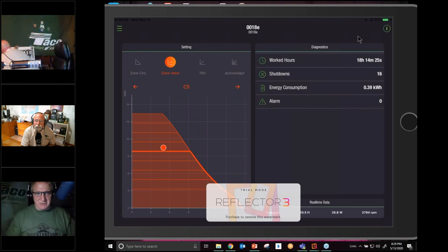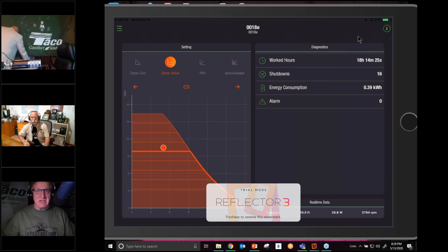So absolutely do that. If you're servicing a boiler and there's a pump on the return and it's dead and you have to replace it, there's no reason not to leave the pump right there. Just swap the dead pump out, put a live pump in, but leave it on the return. That system's been working for decades with the pump on the return. There's no reason to repipe it. You know what I'm saying? You just have to make sure though, Harry, that you use the right circulator.